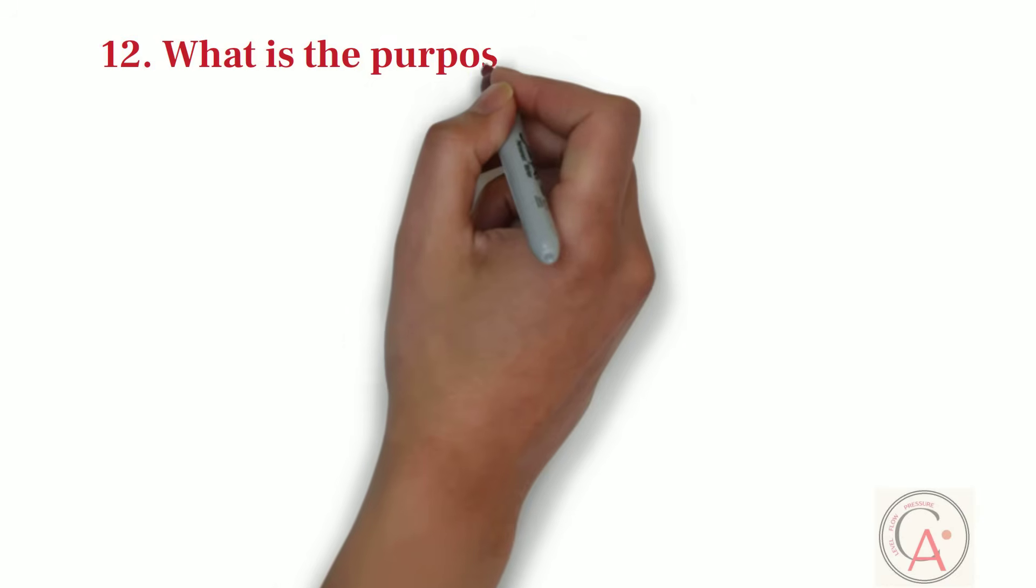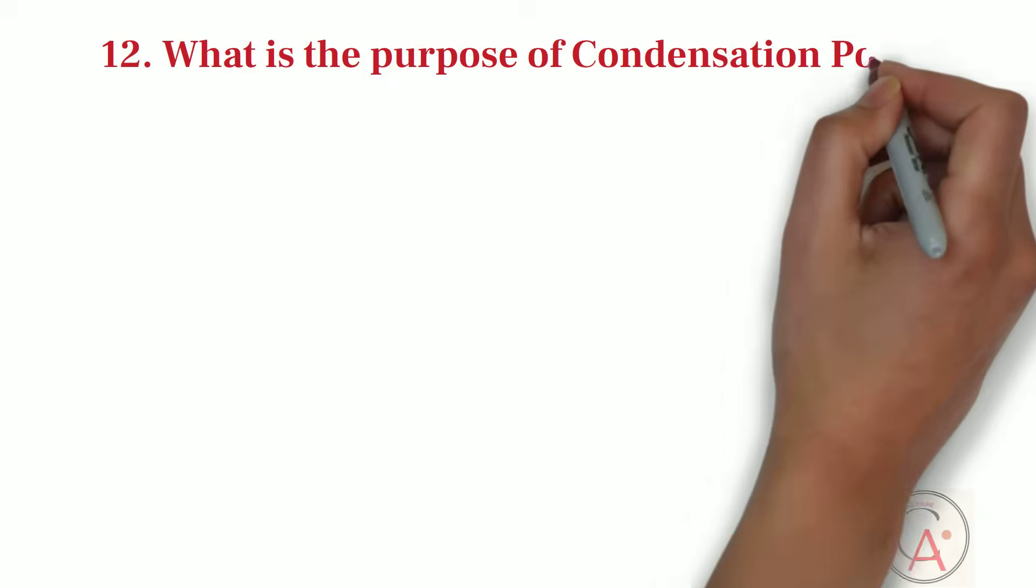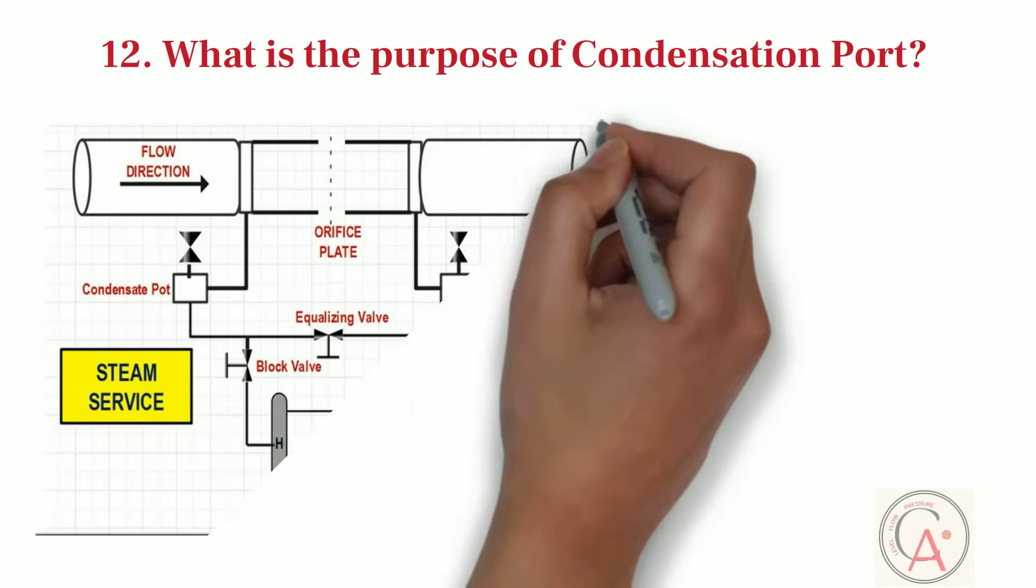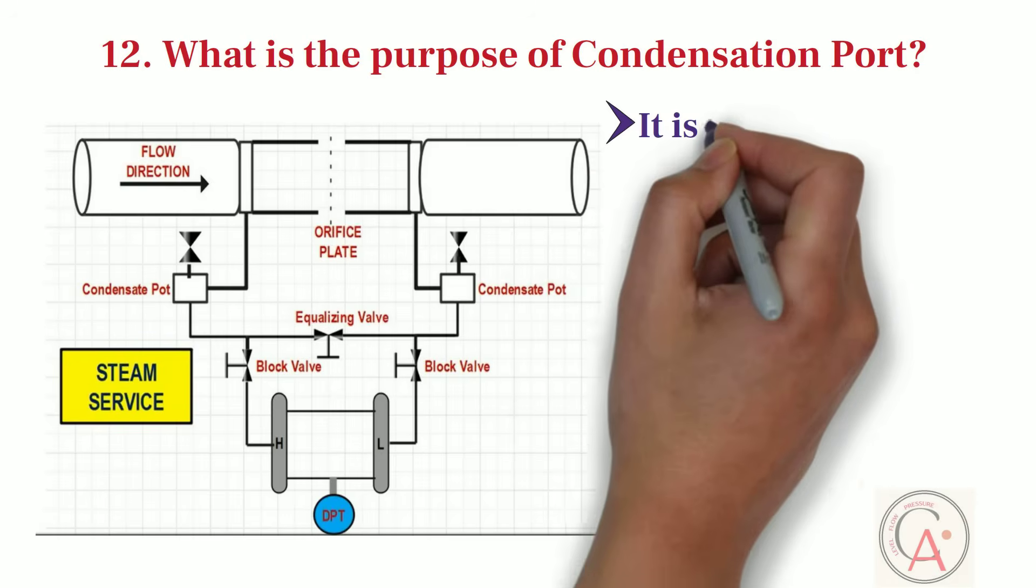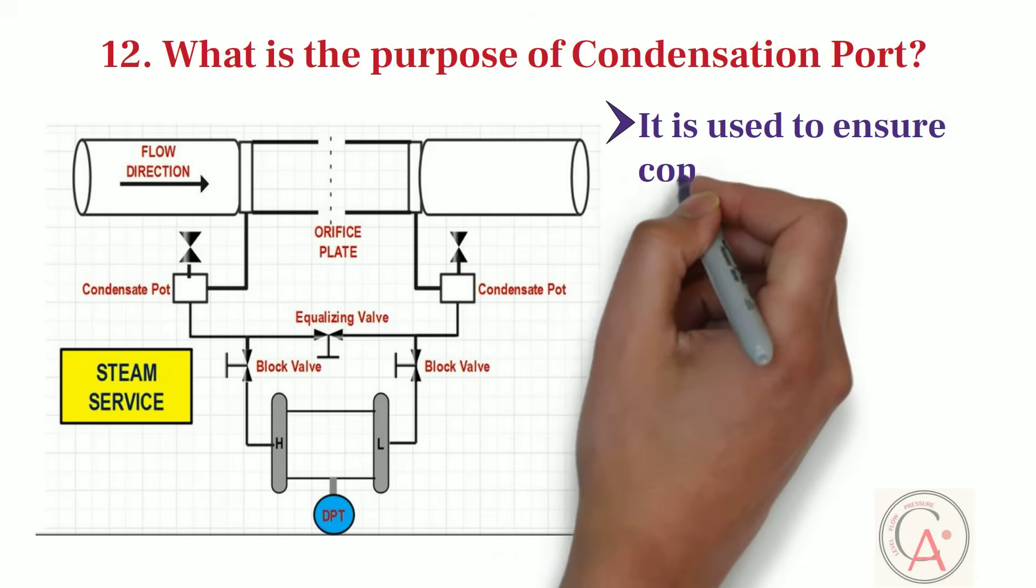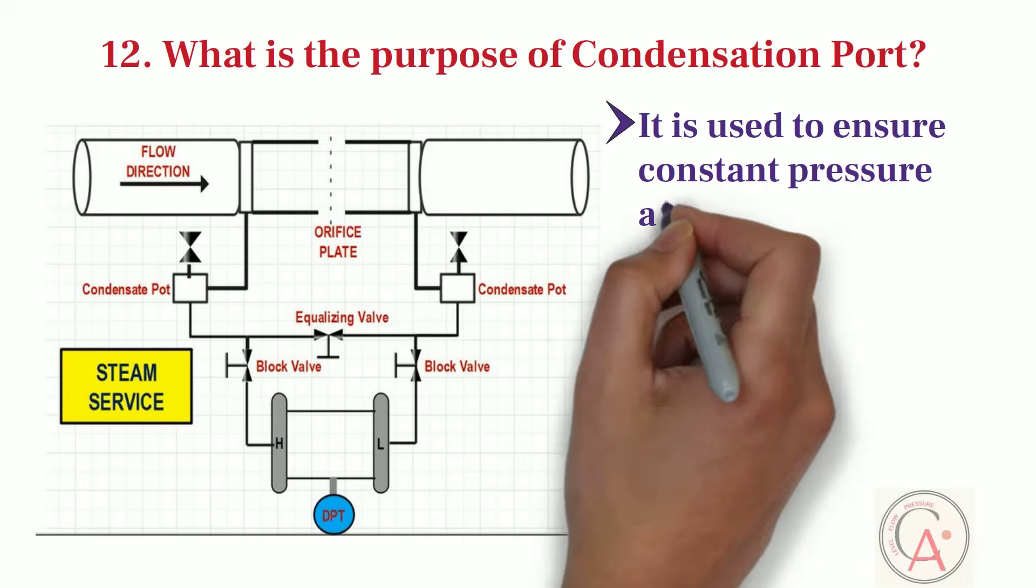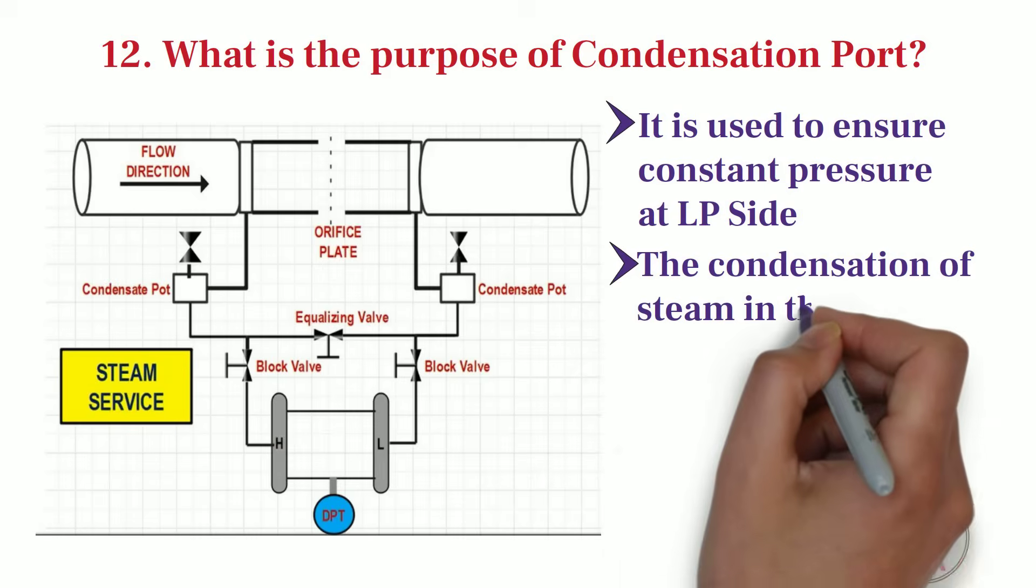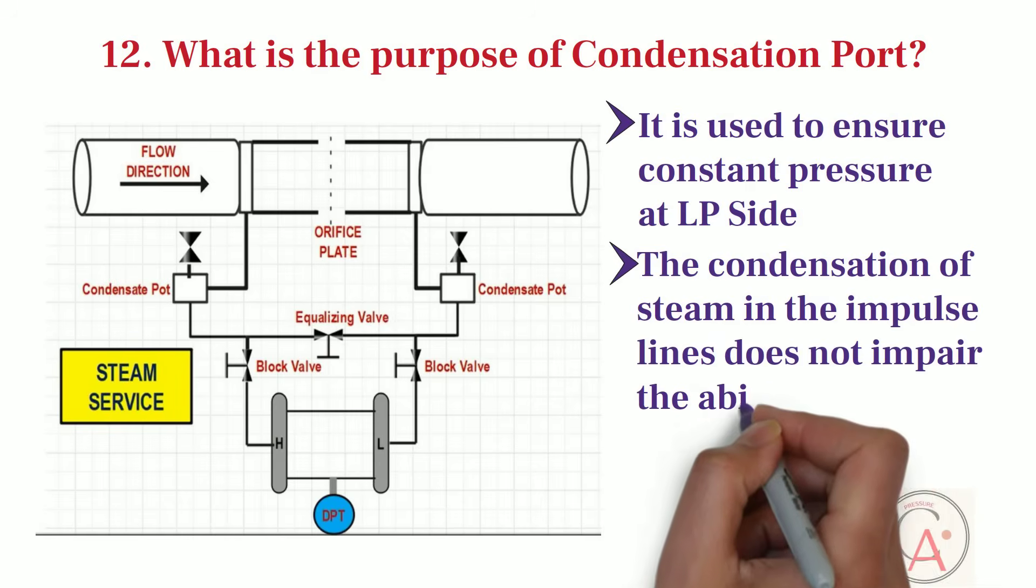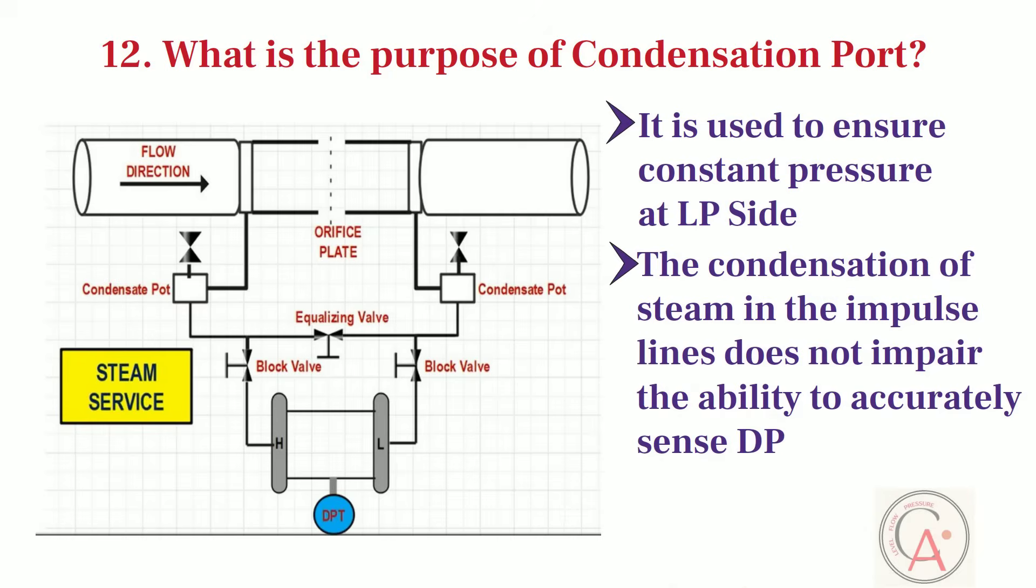Twelfth question is, what is the purpose of condensation pot? There are mainly two applications of condensation pot in steam service. First of all, condensation pot is used to ensure that constant pressure at low pressure side. Secondly, it ensured that the condensation of steam in the impulse lines does not impair the ability to accurately sense differential pressure fluctuations, and to minimize gauge line error.